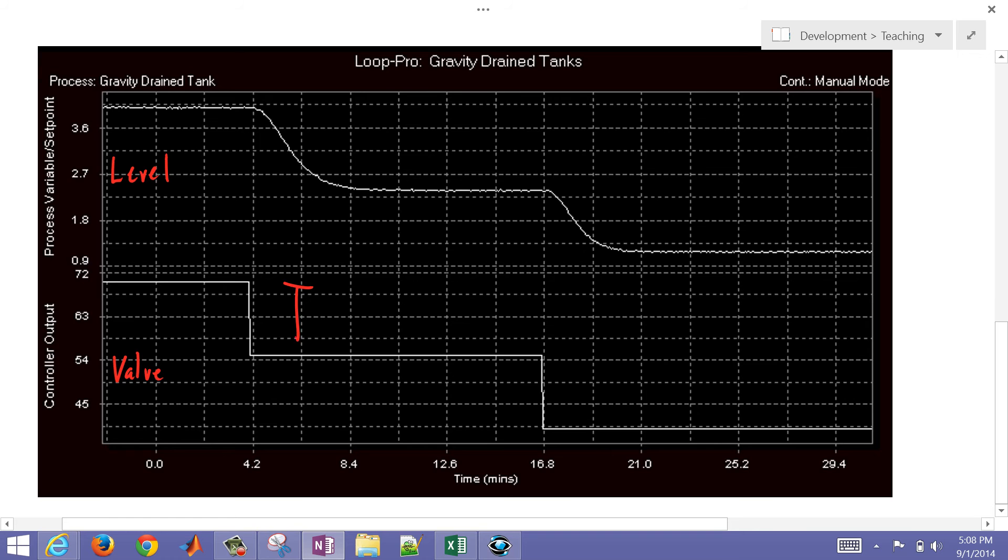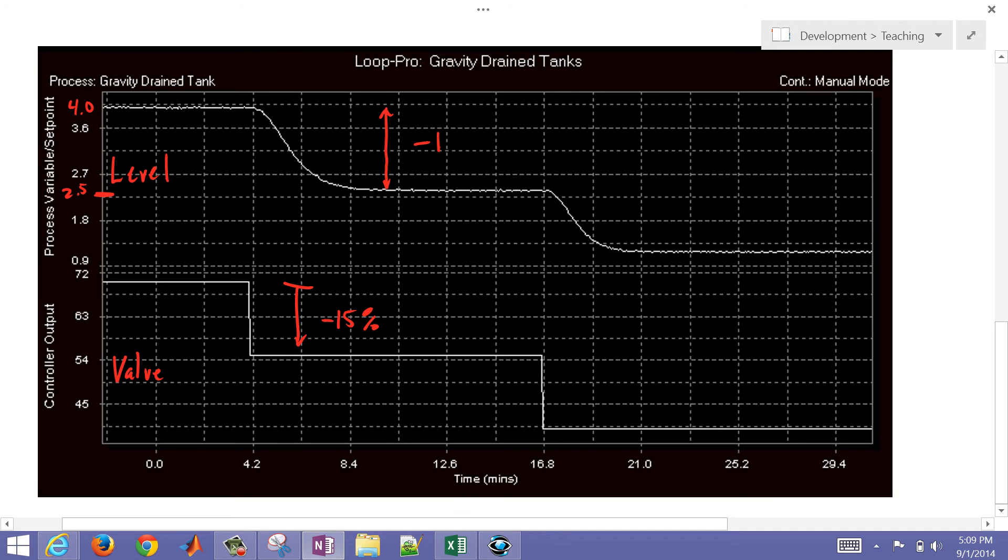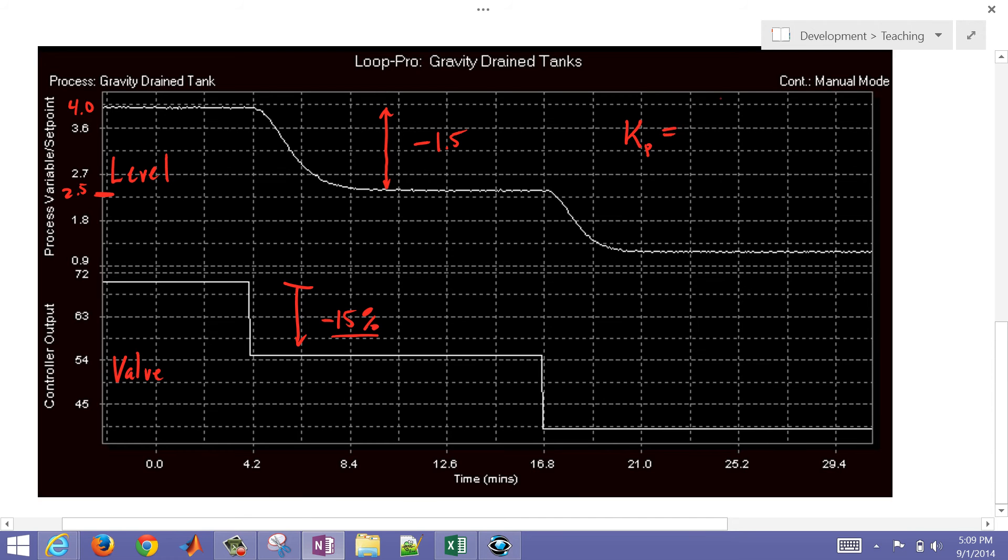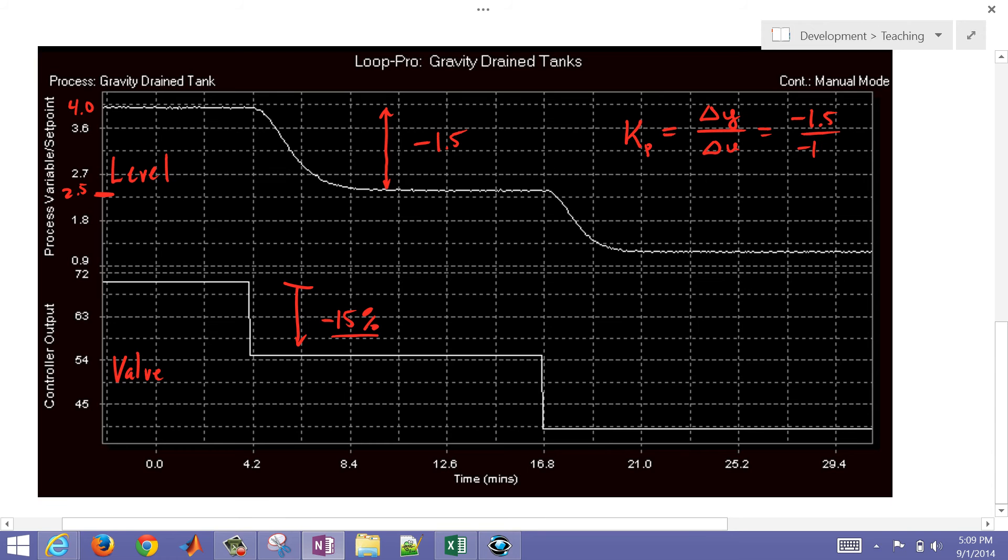So I had the first change was negative 15% on the valve, and then I had a change here. Let's just say this starts at 4 and ends at, let's just say 2.5, just for an approximation. So we had a negative 1.5 level change for a 15% change in the valve. So let's first of all compute our gain. Our Kp is going to be the delta output, the level divided by the delta input. That's going to be negative 1.5 divided by negative 15, so that's going to be equal to 0.1 for the gain. So that's the first thing that we needed.